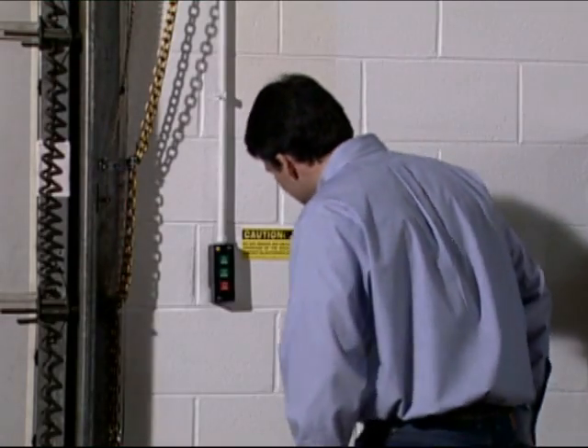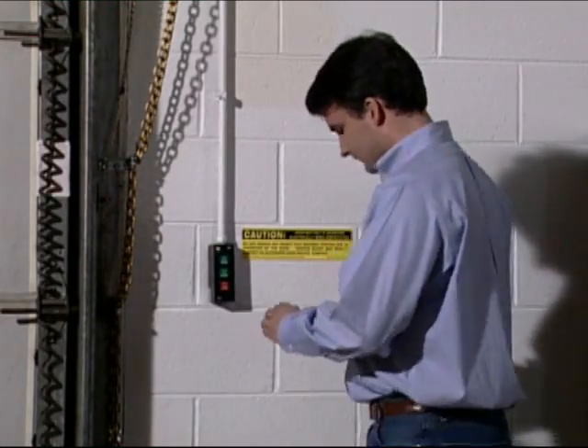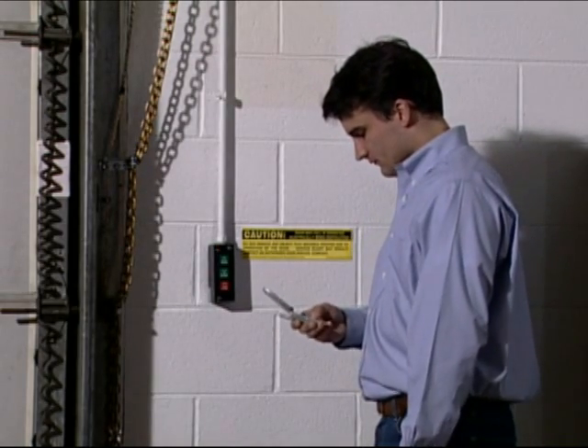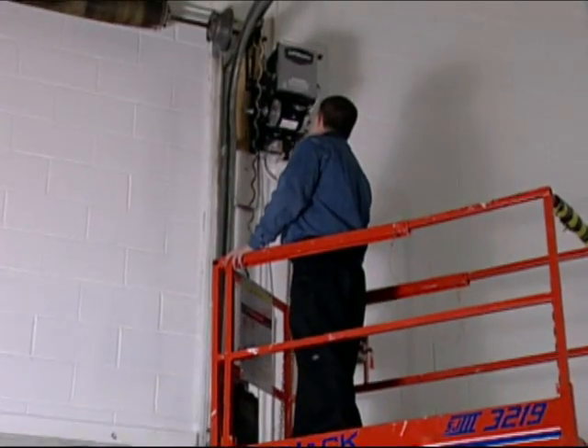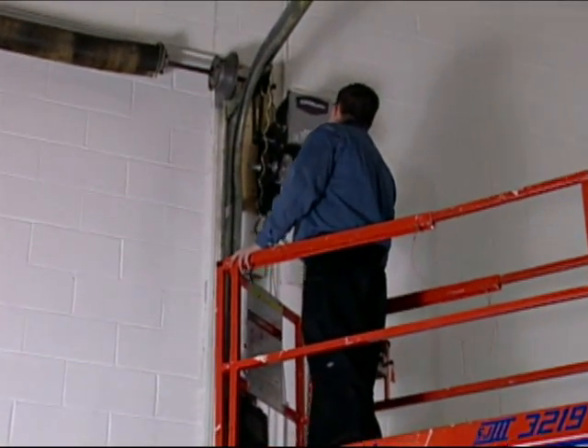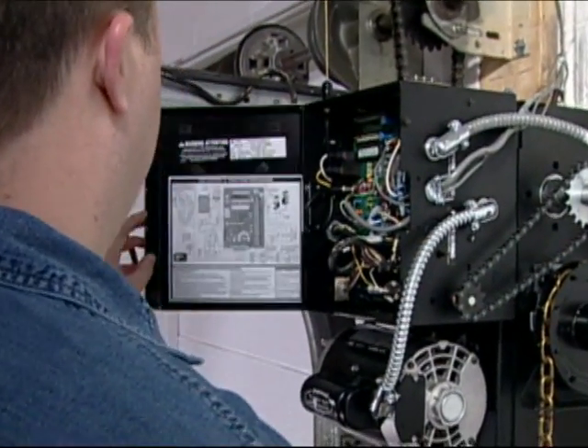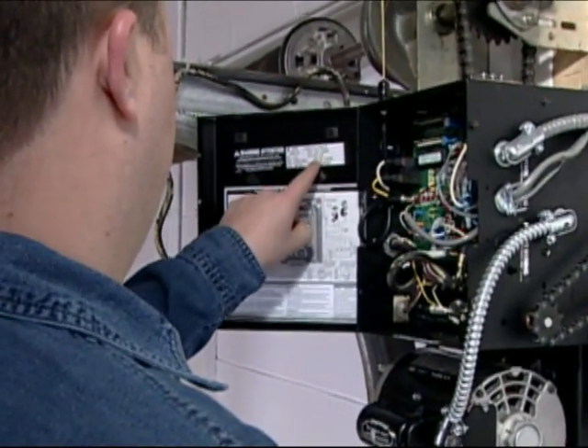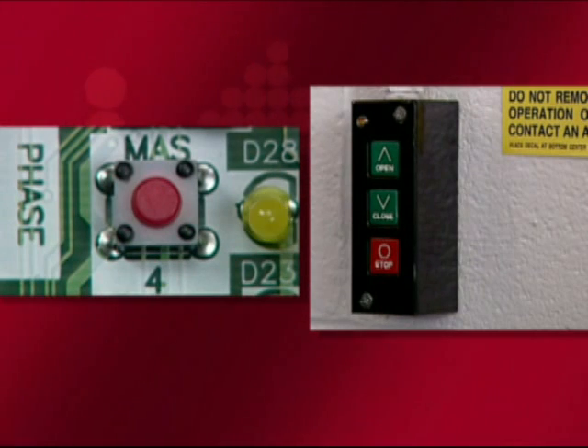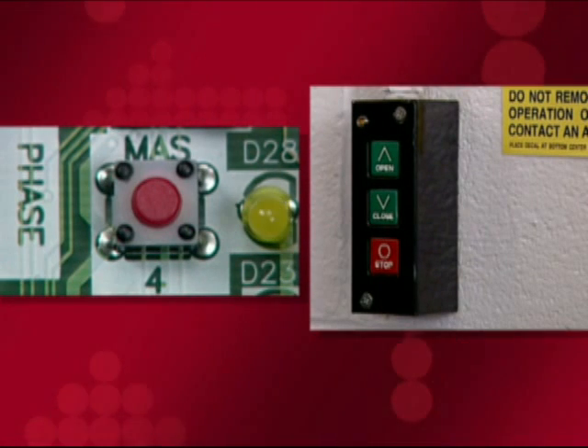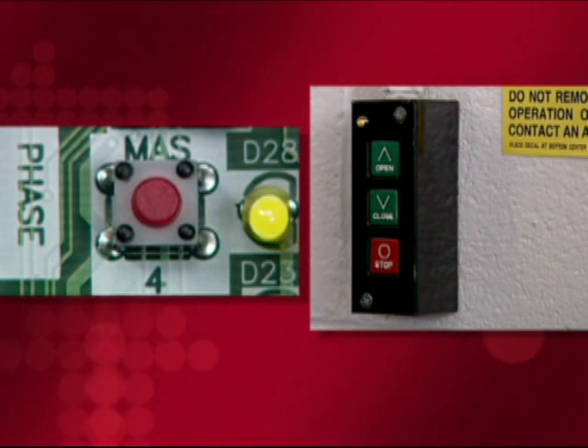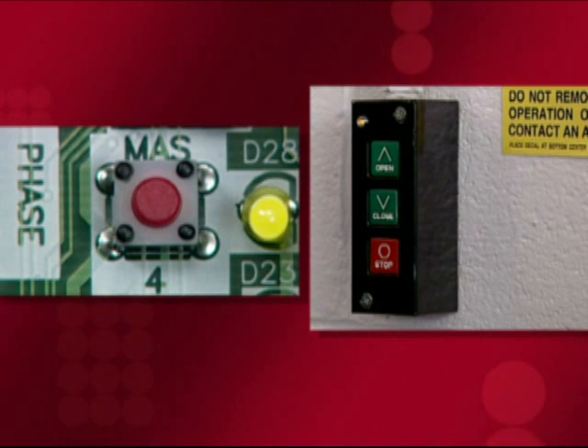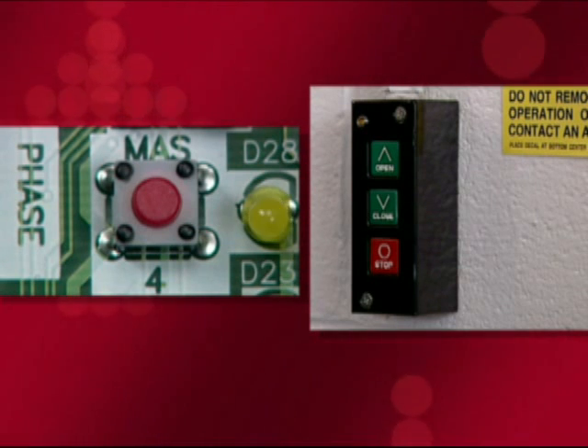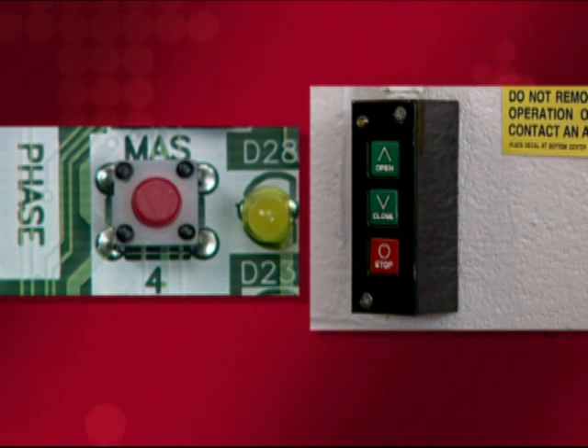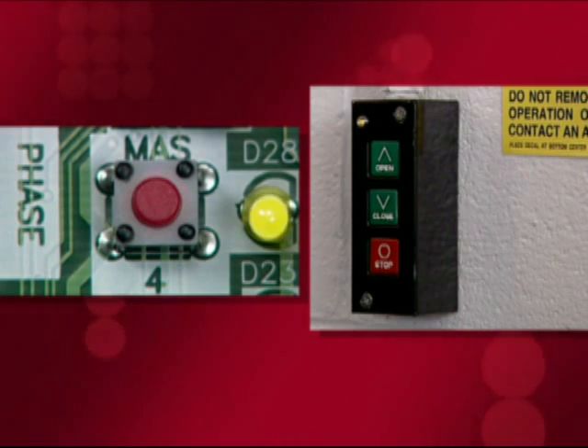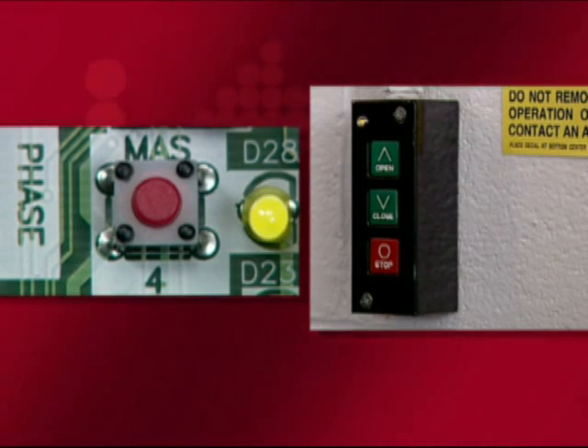In addition to establishing a routine maintenance schedule, the Maintenance Alert System feature includes a self-diagnostic system that allows the installer to troubleshoot up to 8 different error codes. These error codes help speed up installation and troubleshooting. The LED on the 3-button control station and the MAS LED on the logic board will notify you of an error code by blinking slowly, followed by a pause. For example, 7 blinks represents that a fail-safe device has failed or is not connected properly.